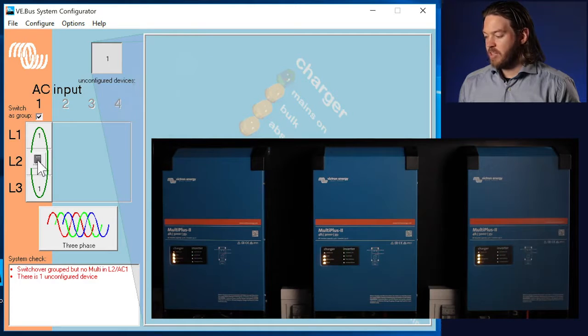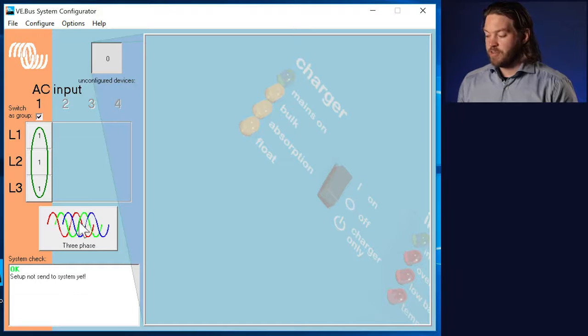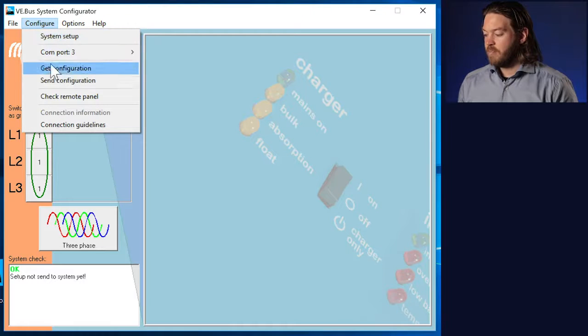I'm now going to drop it in the middle. It's important to get your phases correct to make sure that the incoming phase 1 is matched with the multi that's programmed to phase 1. Otherwise, you can have issues later on with the installation. With all of the units now selected in 3 phase, assigned to the right phase, I can now click Configure and Send Configuration.